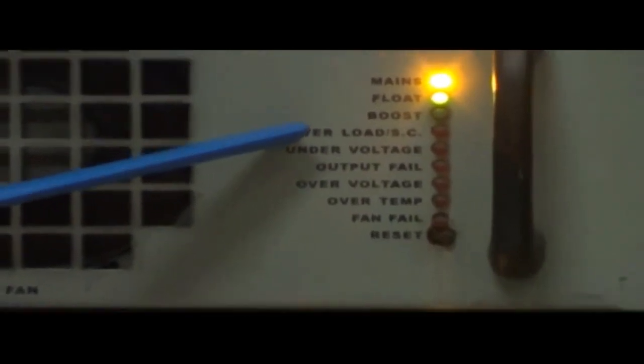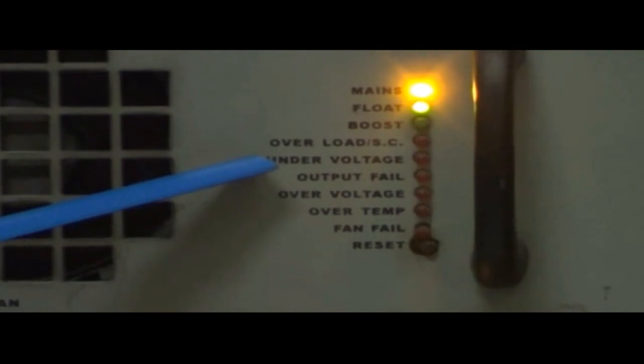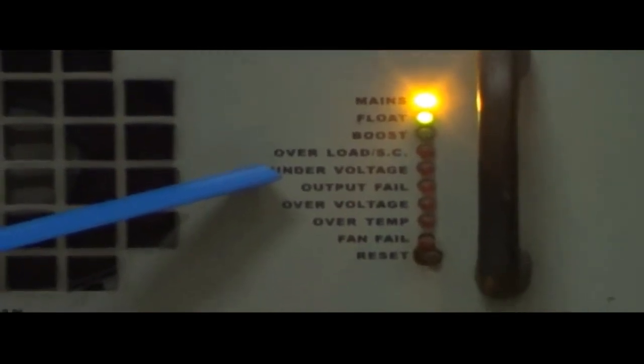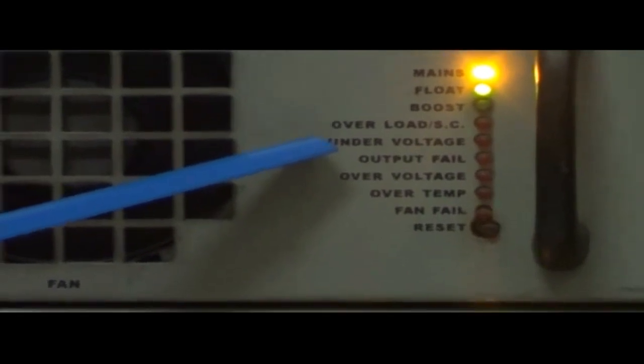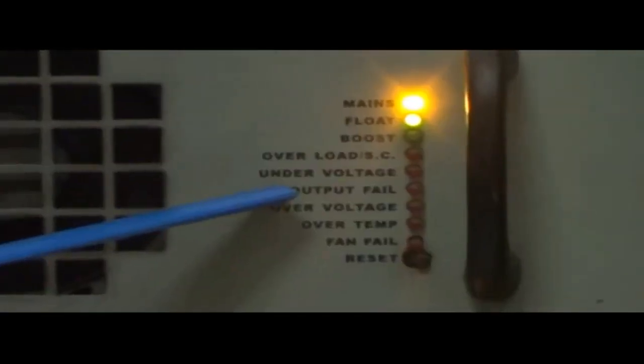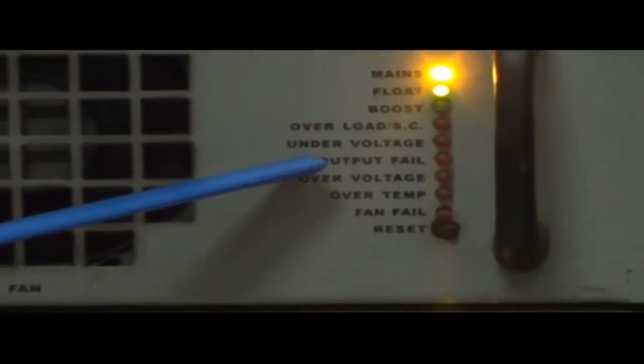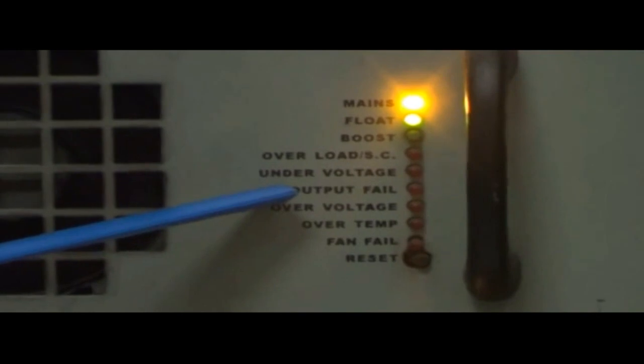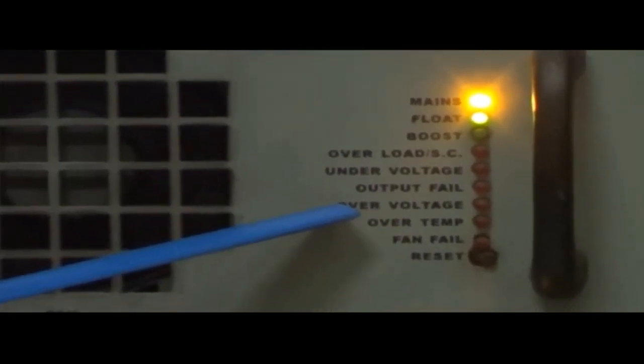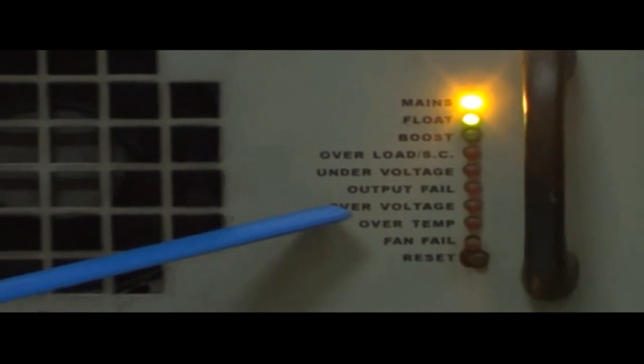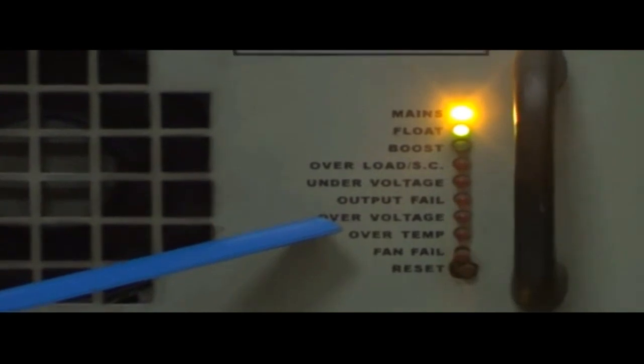Under voltage: This shows that the output DC voltage of the module is low, that is less than 44.4 volts. Output fail: This indication shows that the output DC of the module is not available. Over voltage: This shows that the output DC voltage of the module has exceeded normal output operating range.